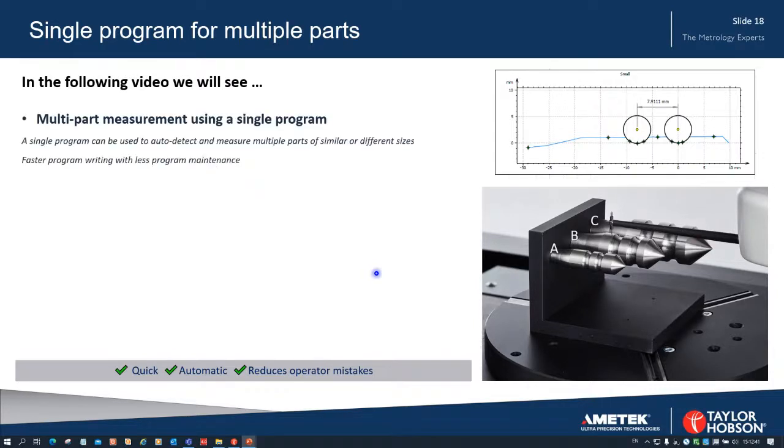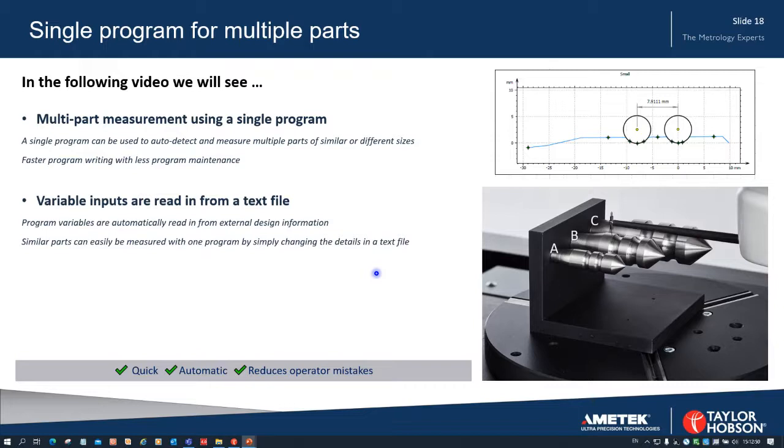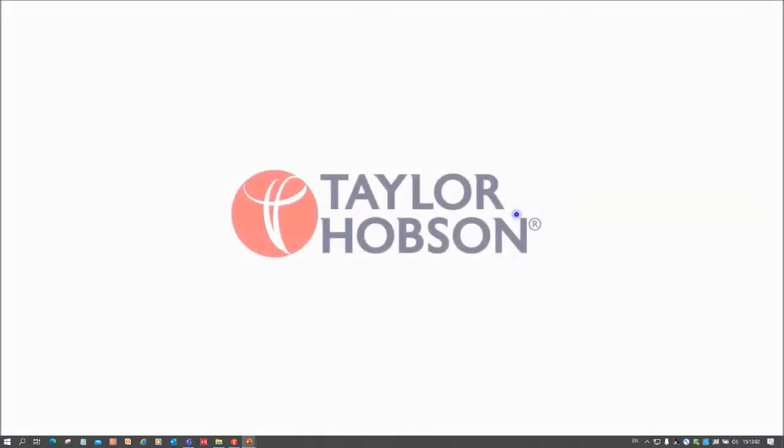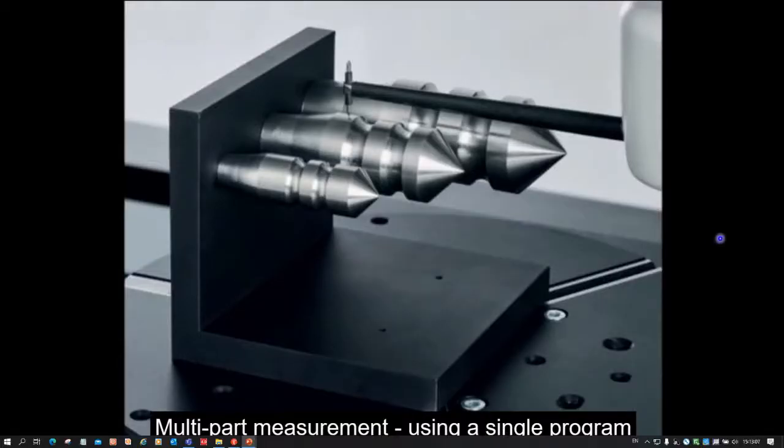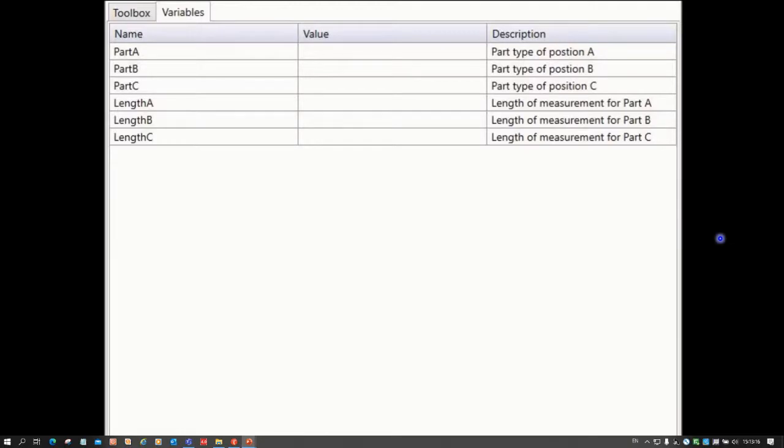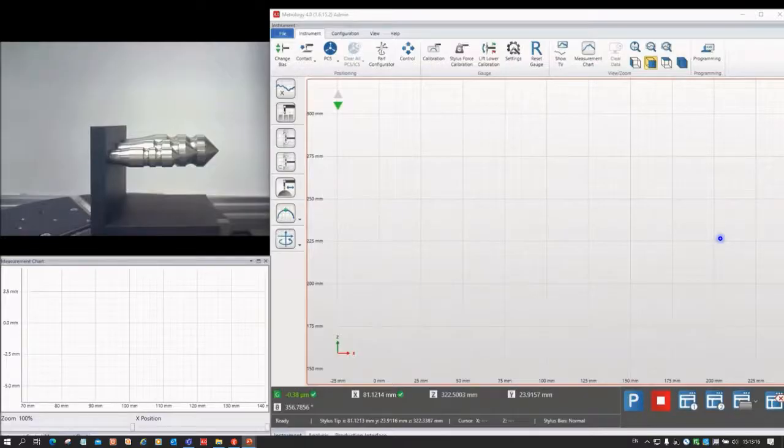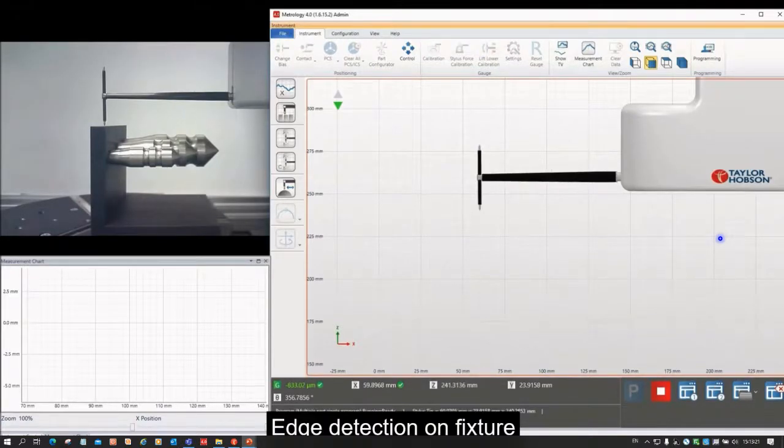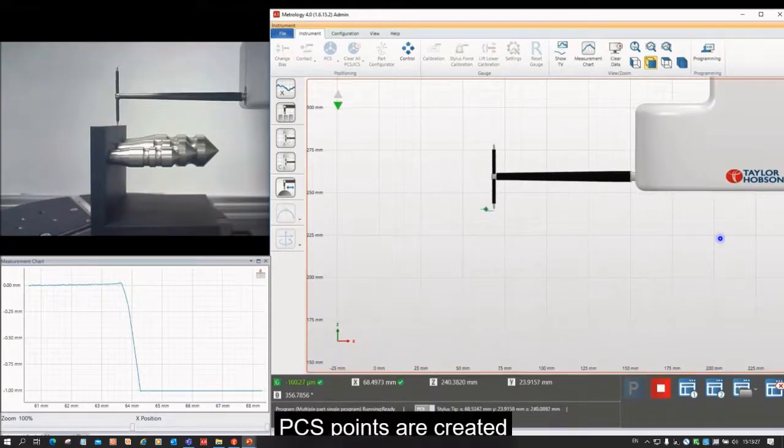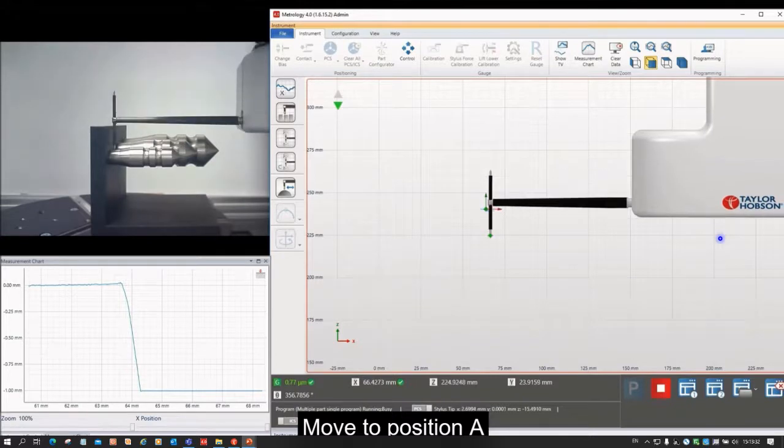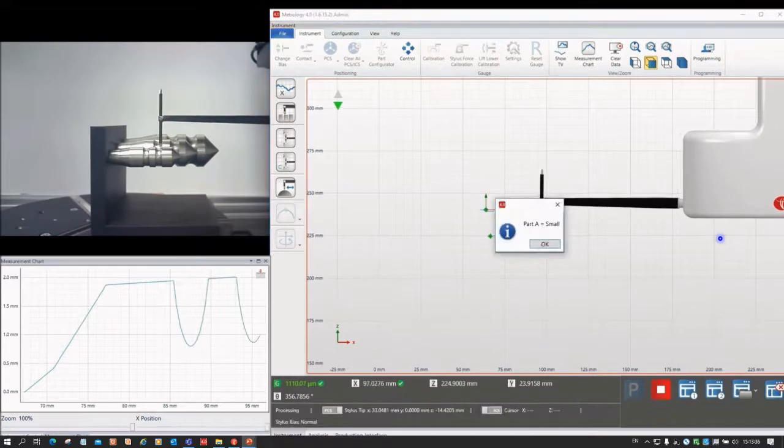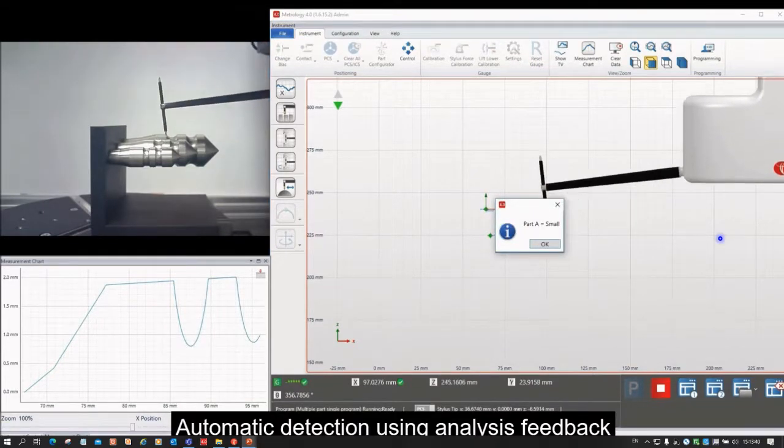So in this video we're going to see multi-part measurement using a single program. We're going to see how the variable inputs are read in from a text file, and then we're going to have a look at some of the analysis. So on the right here we've got the three parts - different sizes A, B, C - and we'll progress now through the video. So there are the three parts. And the first thing that happens is at the start of the program there's no variables there at all. And the stylus now references, in this case, off the edge of the fixture. In the top left you can see it, the part, and it takes a measurement of the part. It's going to move down now to position A, and it's going to measure that short measurement and it's identified that it's Part A, that it's a small part.